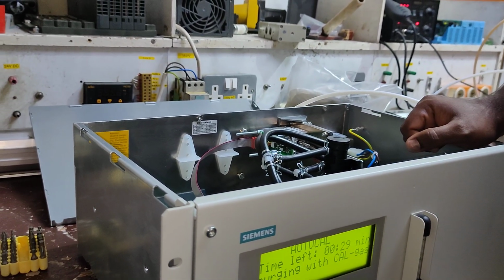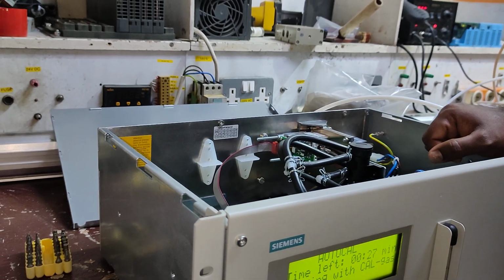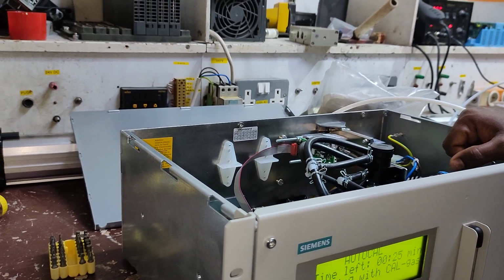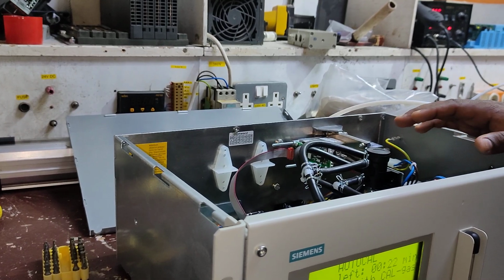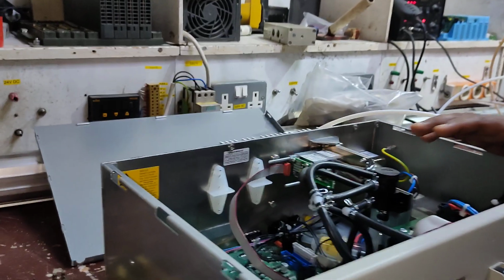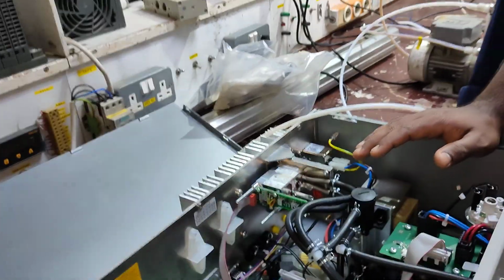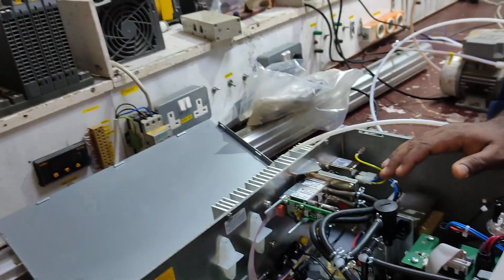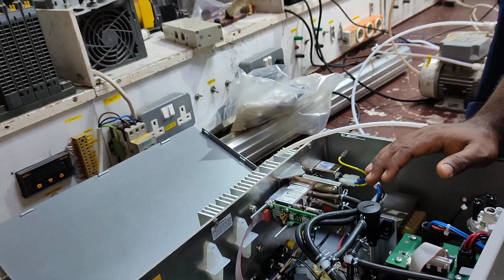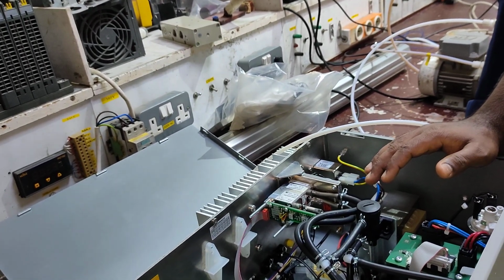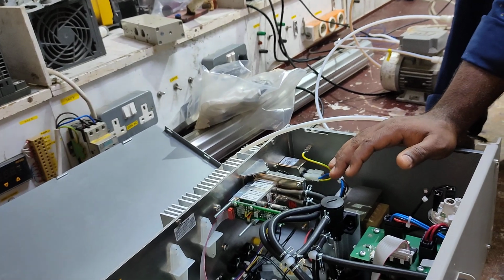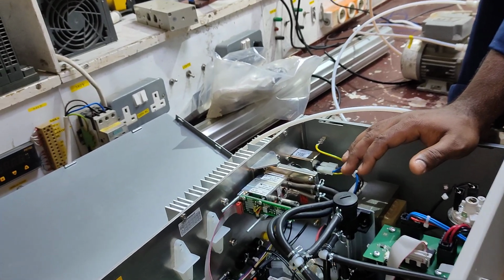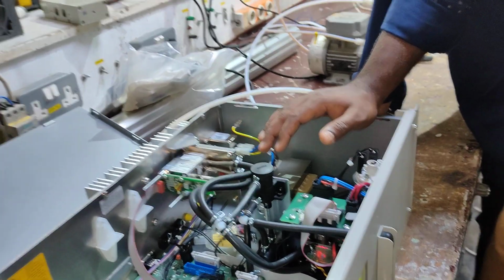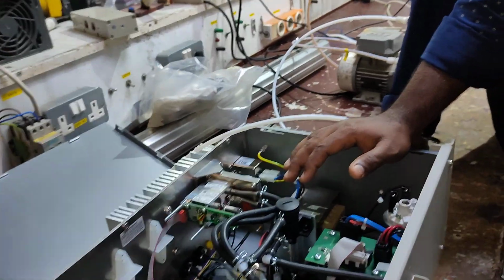So what value difference comes when you are doing with zero gas and air? In air you always have some amount of CO, NO, you are always having it. When you are running nitrogen, you are taking that value, you are not considering that value in your curve. So when you put it in the air and you don't have any CO, you will see a minus value, negative value, because you have not considered the CO, NO of the air. Here what they are doing, whatever is there in the normal air.